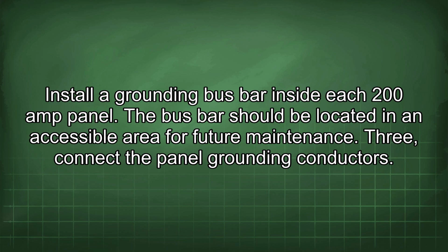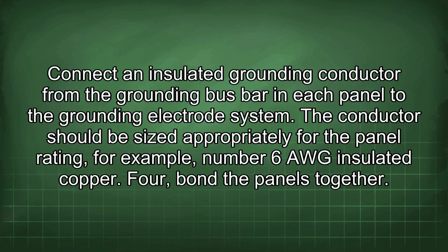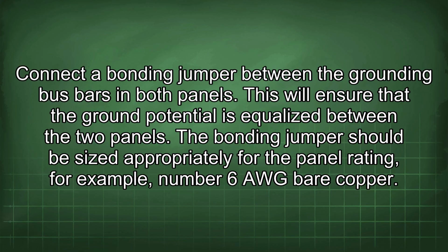3. Connect the panel grounding conductors. Connect an insulated grounding conductor from the grounding bus bar in each panel to the grounding electrode system. The conductor should be sized appropriately for the panel rating, for example, number 6 AWG insulated copper. 4. Bond the panels together. Connect a bonding jumper between the grounding bus bars in both panels. This will ensure that the ground potential is equalized between the two panels. The bonding jumper should be sized appropriately for the panel rating, for example, number 6 AWG bare copper.